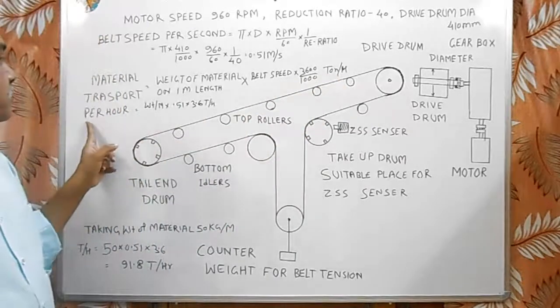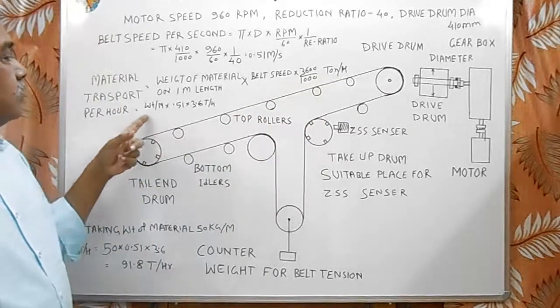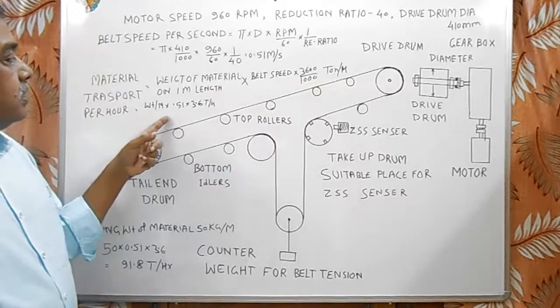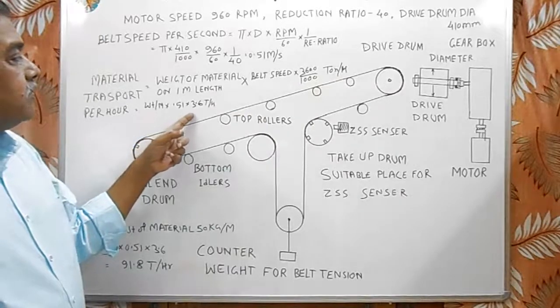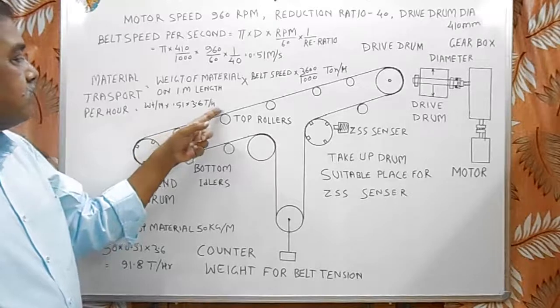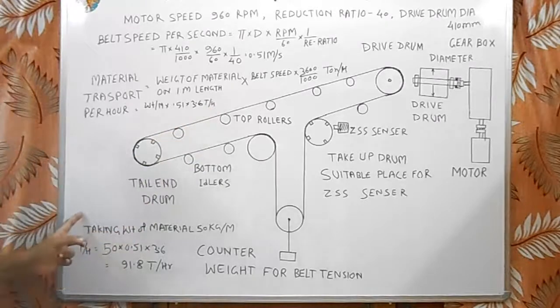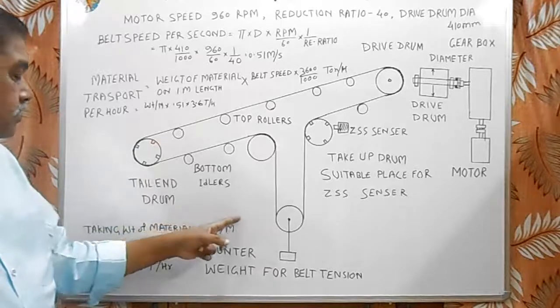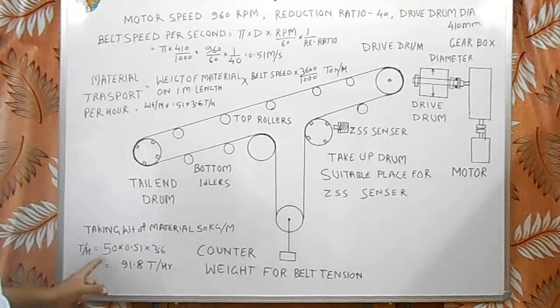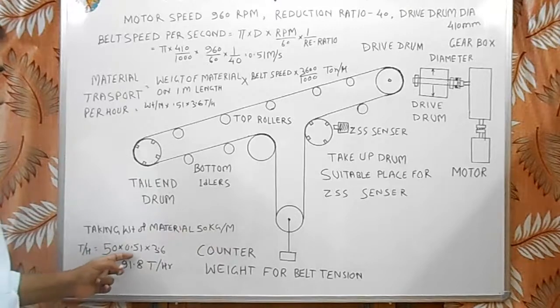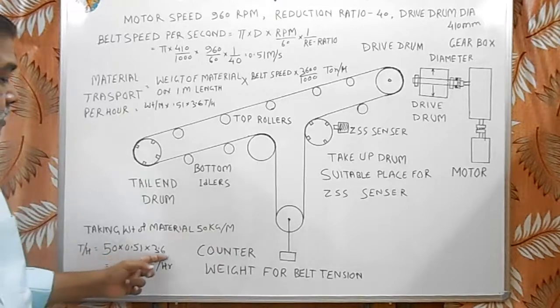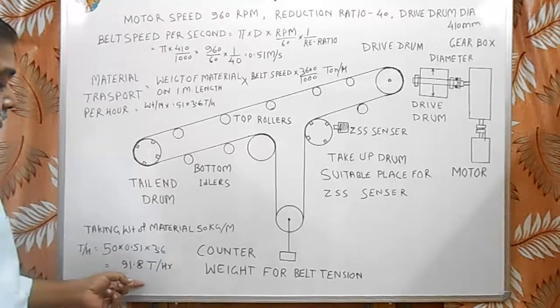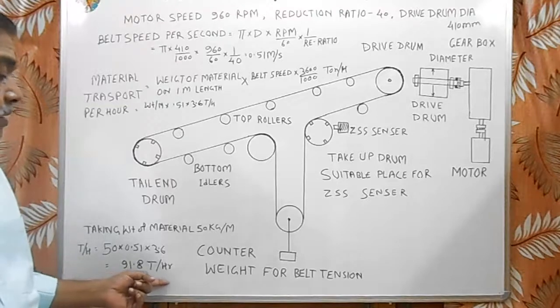Here, this is equal to weight per meter. We are taking weight of material 50 kg per meter. So, calculating tons per hour is equal to 50 into 0.51 into 3.6 is equal to 91.8 tons per hour.